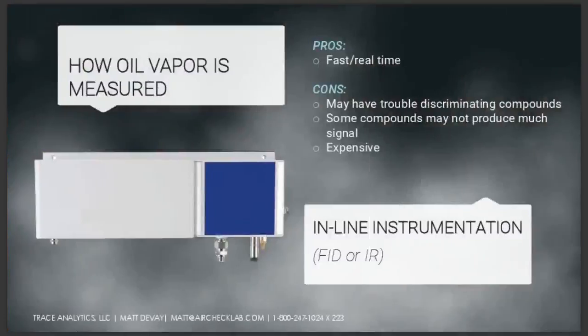All right, oil vapor. So these are the vaporous components. Oil aerosol is liquid in tiny droplet form. Oil vapor is in gas form. So this is one of the more common things that you'll see in some high-end installations: inline instrumentation. These are typically either flame ionization detectors or infrared detectors. Flame ionization detector works by having a little flame, and then it measures changes in the flame as vapors move across it and burn. Infrared uses infrared absorbance to determine the presence of oil vapors. They are fast, they're real time. You get results or information as the gas is flowing through. But they're almost always permanent installs. They're not something that you can carry around from sampling point to sampling point very easily.